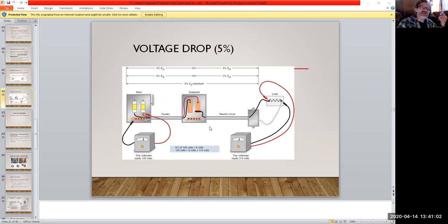And as long as it's within the doable range, you're fine. But again, if you do your formula and it doesn't come out right, yep, next wire size up is what you got to do. So we look and see what we're allowed, and we can't exceed past that point, basically. And again, your voltmeter's your friend.